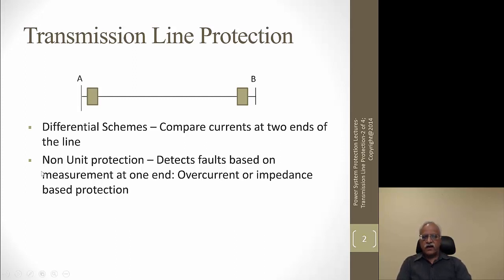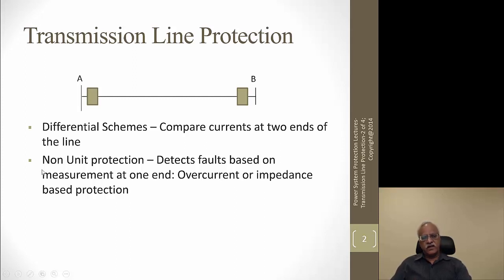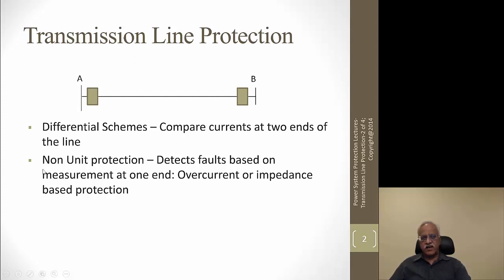Another option is to measure the impedance as seen from line end A or line end B towards the line section. It is a ratio of voltage to current. If a fault occurs, the voltage goes down and current increases, so the impedance measured changes from load impedance to the faulted impedance, which could be just the impedance of the transmission line.